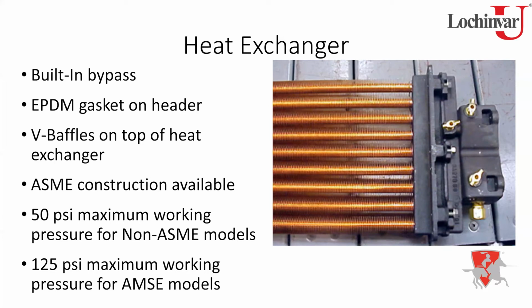Draft is another big thing for those indoor installations, because this unit's going to come to you ready to be installed outdoors. So you do have to put an indoor kit on it so that you can vent the unit. If it's not drafting right, and you have those flue gases pooling inside of that cabinet, they're going to sit there and condense, and they're going to start to eat away at that copper heat exchanger. So if you ever get in here, those are a couple of things that can cause that green buildup on top of that heat exchanger.